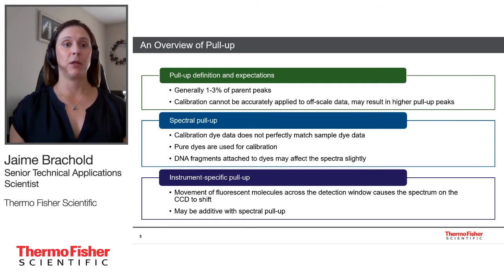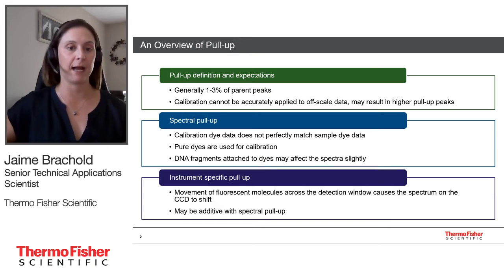If there is instrument-specific pull-up and spectral pull-up in the same dye channel at the same time, they would be additive. So you would see maybe a single pull-up peak, but the percentage might be slightly higher.